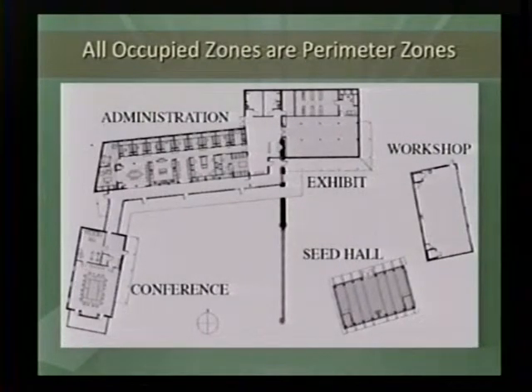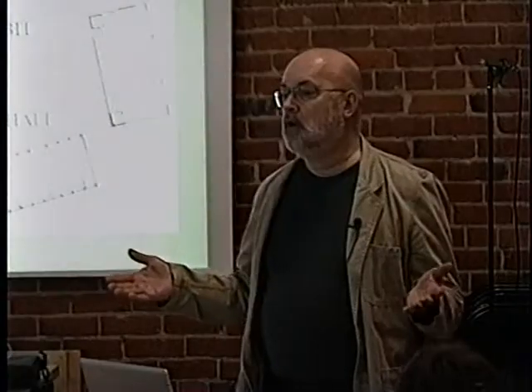They can have up to about 120 people in there. There is no HVAC system in that building. It is only operated from mid-March through late October. There is a wood-burning stove. There are window panels that can be removed and replaced by screens. It's basically a screen porch that's not attached to a building. And the windows aren't removed until you get to the main summer condition. There are some transoms that can be opened in spring or fall for ventilation. So it's basically a naturally ventilated building with a wood heating stove and no other mechanical system.